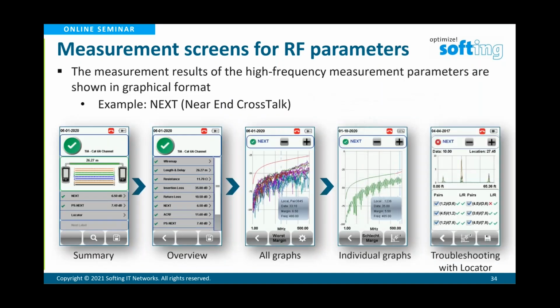The RF, or high frequency, parameters can be shown in graphical format, usually only on the local unit. We have a combination of two screens across both units: a local screen with a white background and a remote screen with a black background. You can see results in numbers on both sides, including the wire map and distance to faults, but the frequency graphs are only visible on the local unit, where they are stored and from where we can import them into the software.